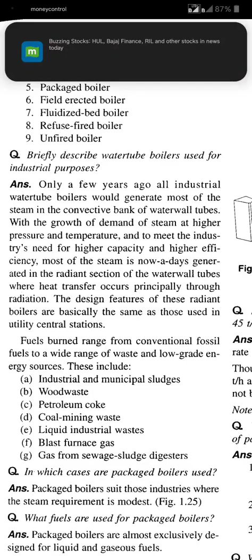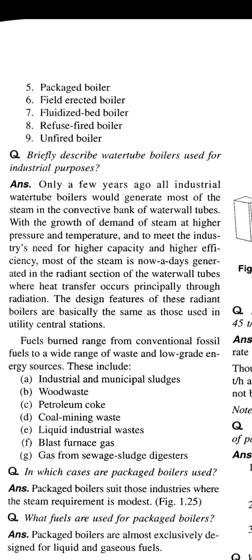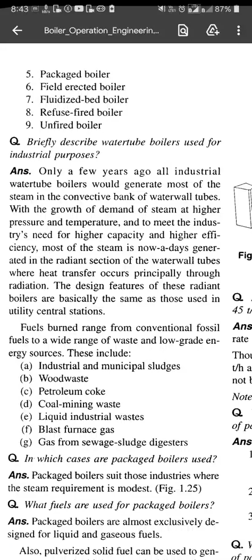Answer: only a few years ago, all industrial water tube boilers would generate most of the steam in the convective bank of water wall tubes. With the growth of demand for steam at higher pressure and temperature, and to meet the industry need for higher capacity and higher efficiency, most of the steam is nowadays generated in the radiant section of the water wall tubes, where heat transfer occurs principally through radiation.